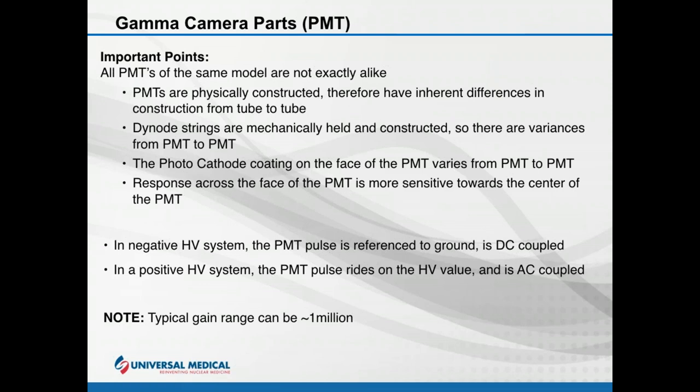Things to think about: photomultiplier tubes are not all exactly alike — they are physically constructed items and there will be differences from tube to tube, including how dynodes are aligned, and variances in photocathode coating from PMT to PMT. Even the response across a single PMT can vary from left side to right side. PMTs come in two basic families: negative high voltage and positive high voltage.